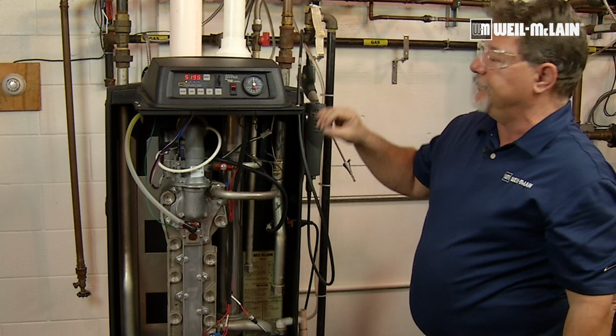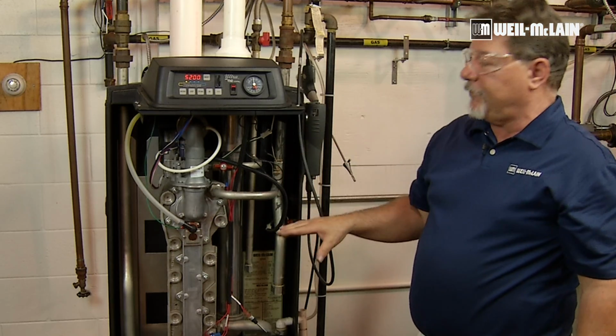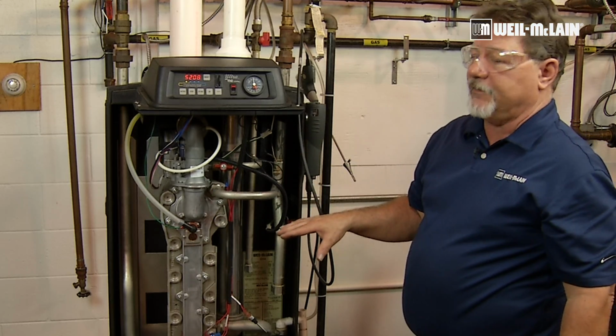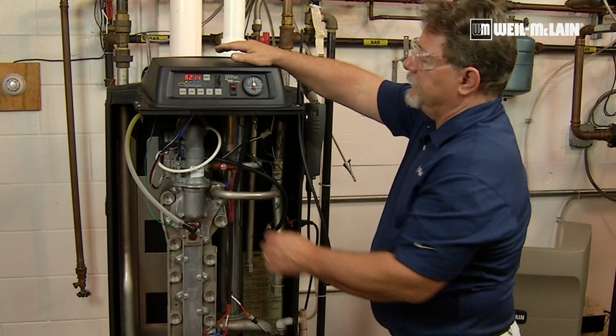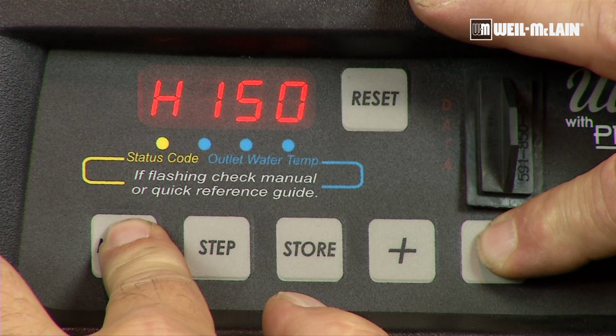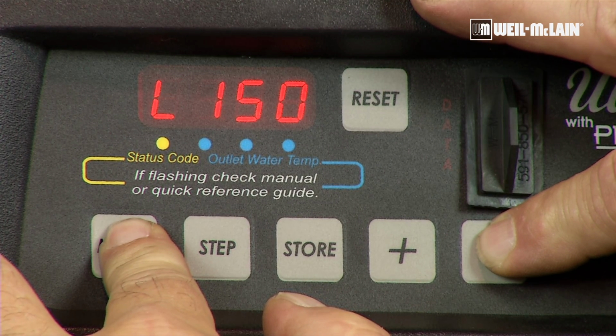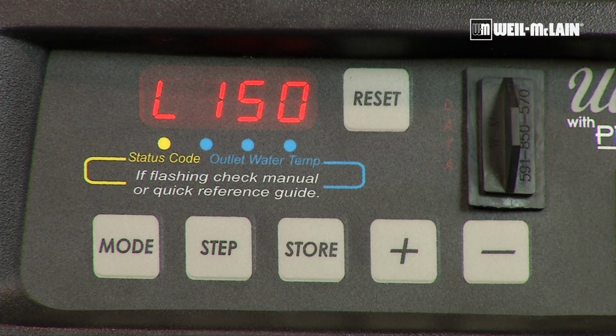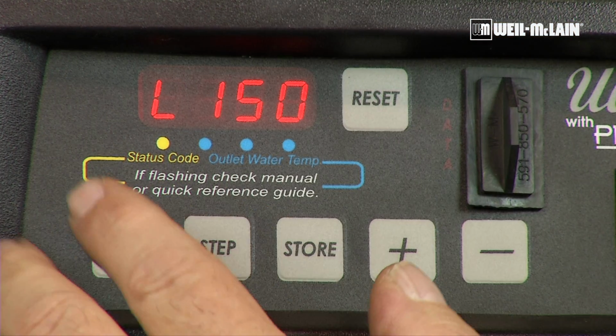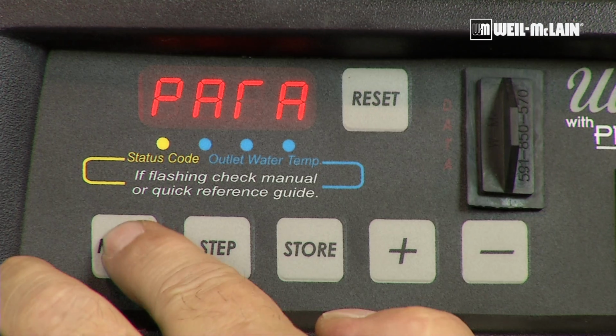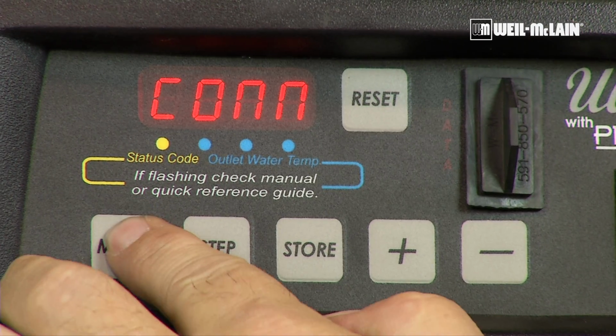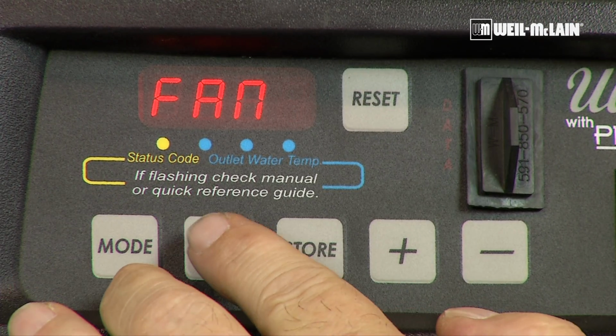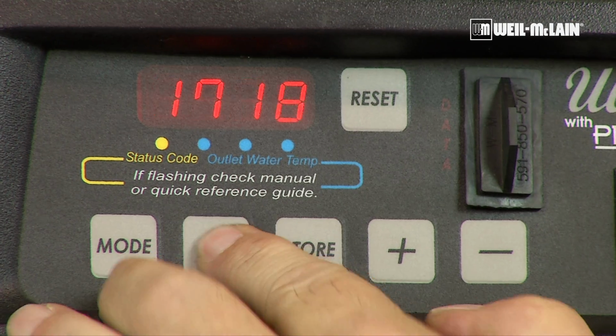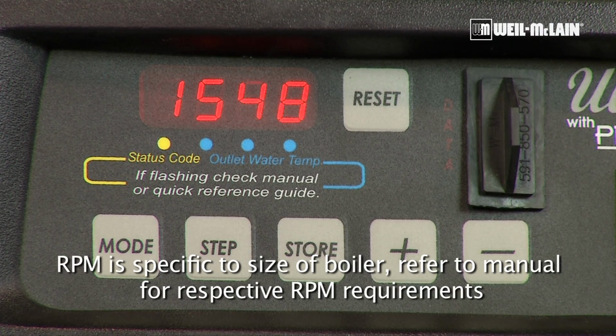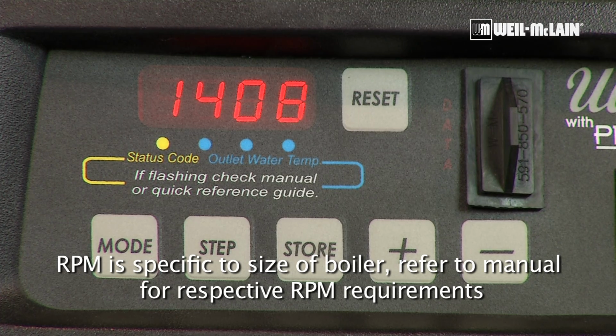Next, I want to go down and improve my low fire combustions. And to do that, I have to be in the standby mode. I'm going to hit the minus button and the mode button simultaneously. By pressing the mode button into the fan file and opening it up via the step button, we'll see the boiler spool down to low fire. 1200 RPM is the low fire.